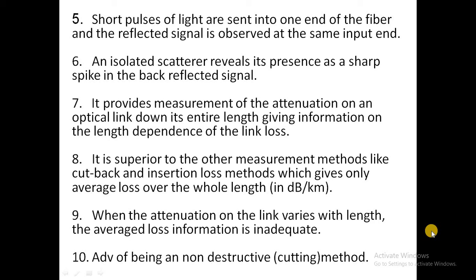It is superior to other measurement methods like cutback and insertion loss methods, which give only the average loss over the whole length in dB per kilometer. With the other techniques, cutback and insertion loss, damage can occur due to the cut if you are cutting the optical fiber. That is also a drawback of using the other methods instead of the OTDR.